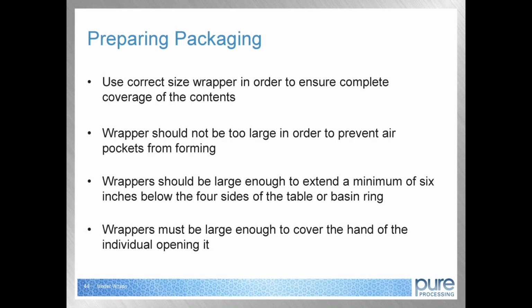AST's standard of practice states all wrapped packages should be prepared to facilitate ease of opening the package and transferring to the sterile field while maintaining the sterility of the contents. To do so, facilities must use the correct size wrapper in order to ensure complete coverage of the contents and sterilization. The wrapper should not be too large, in order to prevent air pockets from forming. This can inhibit the penetration and release of the sterilant. It should not be too small, as to not allow adequate coverage of the contents and possibly tear at the corners.